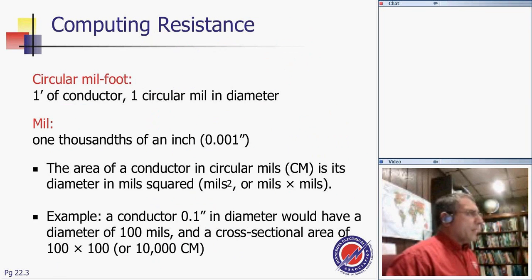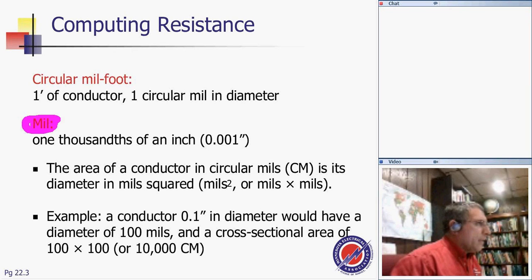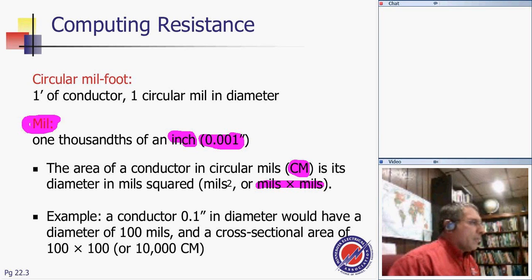There's a concept, and I will get back to these rules. Please write them down because I will use them in a few seconds. Now, the circular mil is an interesting phenomenon. I don't know if you guys know, a mil is actually one thousandth of an inch. You have a circular mil because that's how we measure the cross-section area in the U.S. Circular mil means a mil squared, a mil times a mil. So if you take 0.001 and multiply it by 0.001, that will give you a circular mil, basically. That's a quick example to understand what a mil is.